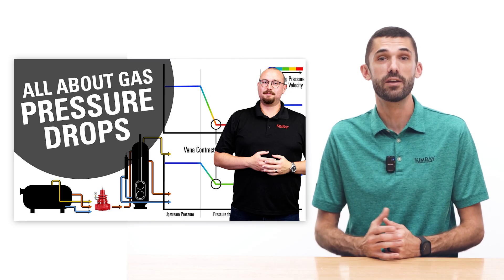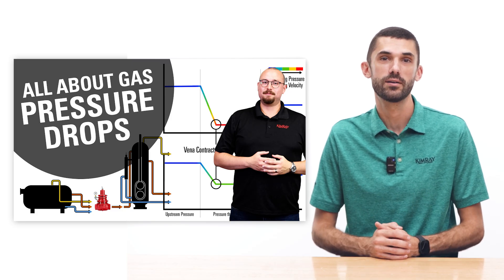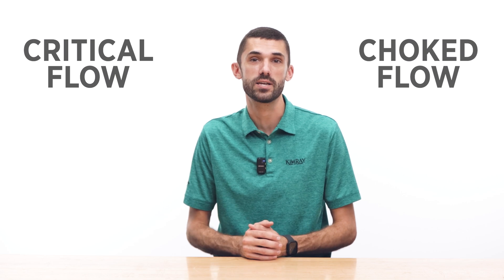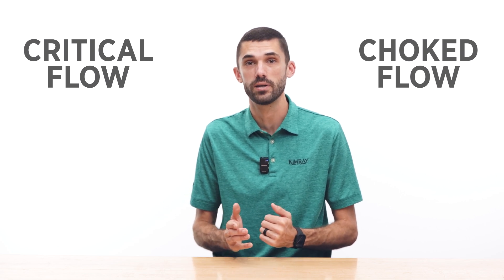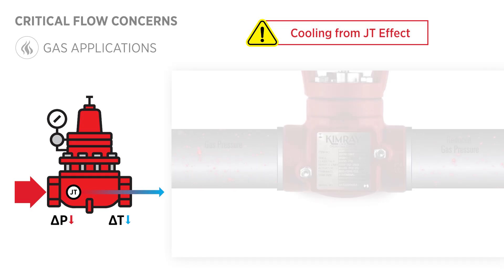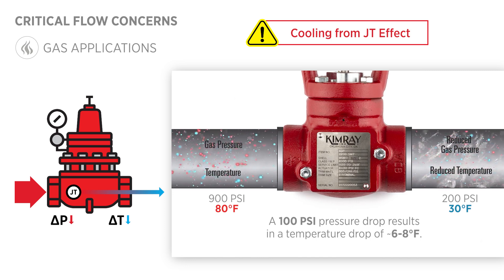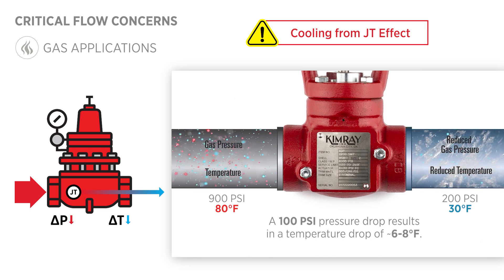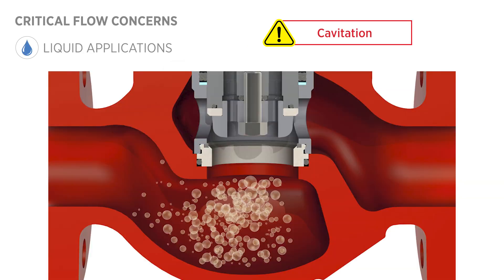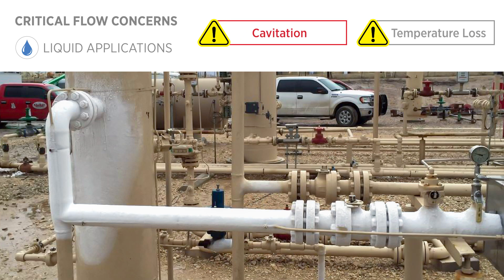For more on cavitation and flashing, check out our blog. While not technically identical, in valve sizing the terms are used interchangeably and both have concerns to be aware of. In gas applications, the main concern is cooling from the Joule-Thompson effect — for example, a 100 psi drop causes about 6 to 8 degrees Fahrenheit of temperature drop. In liquid applications, the main concern is cavitation, which can damage the valve internals and increase the chances of water hammer. Temperature loss is also a concern with liquids because they could freeze and block flow.